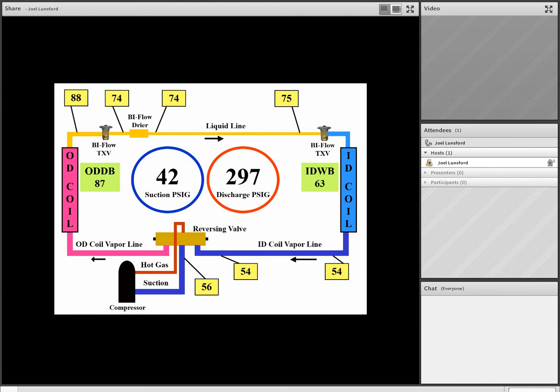So we can reach the conclusion then, we know we have a liquid circuit restriction with low suction pressure, high discharge pressure, elevated or high subcooling, and high superheat means a liquid circuit restriction. And as we start taking temperatures across the liquid line components, we see we have a 14-degree temperature drop across the biflow TXV outside that should be flowing freely through its check valve circuit. And we should have no temperature difference, maybe 1 degree maximum, but no significant temperature difference. So we have 14 degrees. So our diagnosis in this one is we have a liquid circuit restriction. The outdoor TXV check valve circuit is restricted. And there we go, restricted outdoor TXV check circuit.